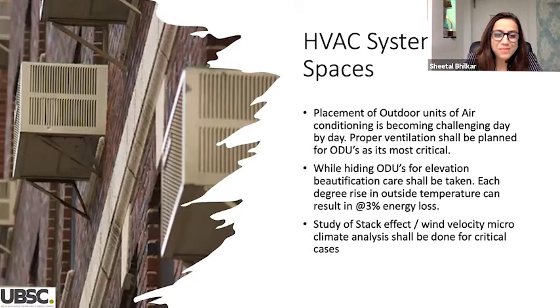Outdoor unit locations are becoming day by day a very big issue for high rises, because of the placement of ODUs. Likewise in Mumbai, you really don't get space for all these things. But proper ventilation of the ODU is very important, because every degree rise in outside temperature leads to 3% energy loss. So you should always think strategically while placing the outdoor units. Also, you have to study the stack effect. If multiple outdoor units are placed in a duct, you have to think of the stack effect at that time.